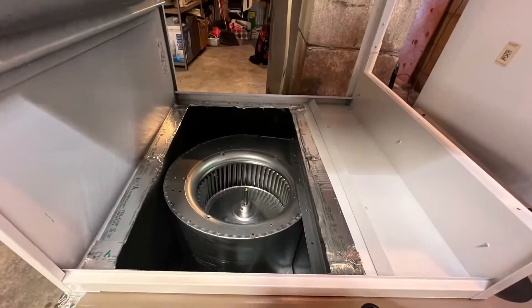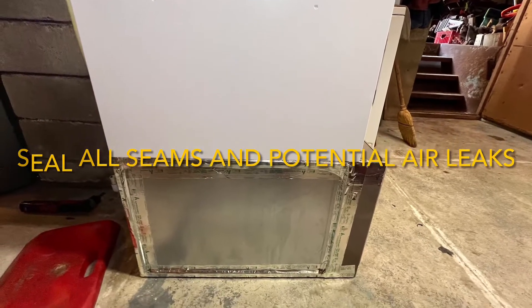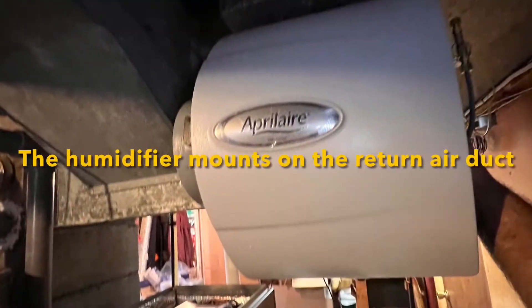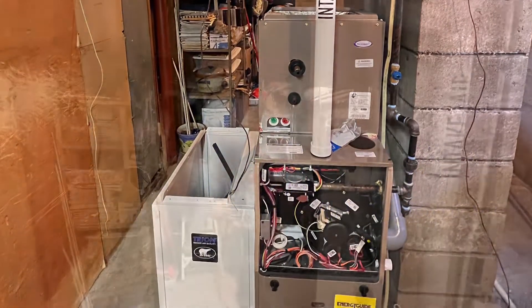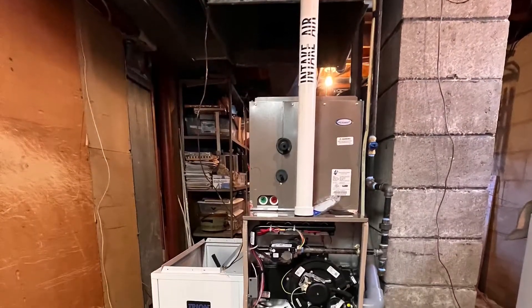So we ended up having to change out the system. We got him a new York Affinity high-efficient 97.5% efficient gas furnace with a 13-SEER York outdoor R410A ozone-safe refrigerant condensing unit. We ran all new piping to the unit, added a new Aprilaire central humidifier, completed all the sheet metal work and new refrigeration piping and electrical wiring needed.